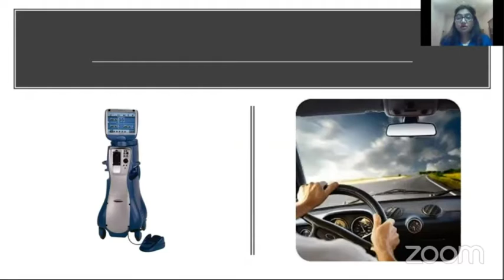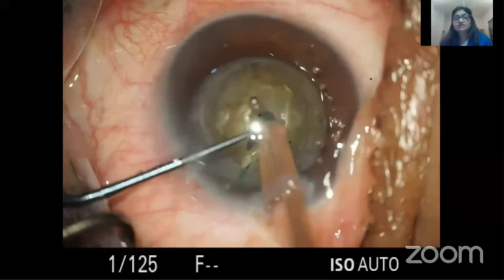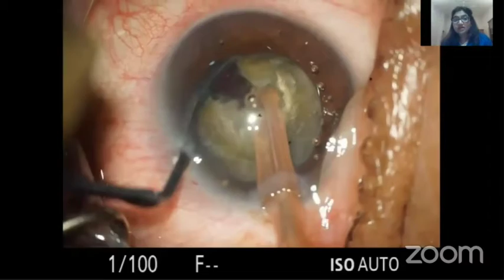This is a hard cataract. In sculpting, you do not need much of vacuum or flow rate, but you need better cutting. So here your phaco power will be more, but it need not have more flow rate or vacuum. But when you are chopping the nucleus, this is where you will need more vacuum, but only when you are chopping, you need not have more flow rate, because you don't really want pieces to be coming close to the tip. You just want better cutting and you want better holding at this step.